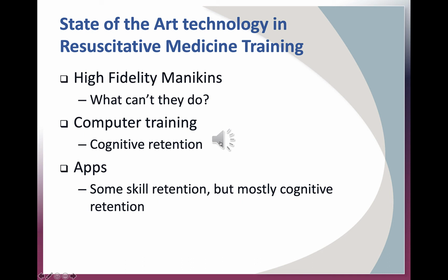For resuscitative medicine specifically, these mannequins can tell what medications are being given, if the chest compressions or breaths are adequate, and they can track all of this and give feedback. They can also respond very quickly. If the incorrect medication is given, or if the compressions cannot sustain life, the mannequin would not be revived. In addition, one operator is needed currently, whereas in the past it needed a couple operators, and the operator can be in a different room, making just the mannequin there looking as realistic as possible.